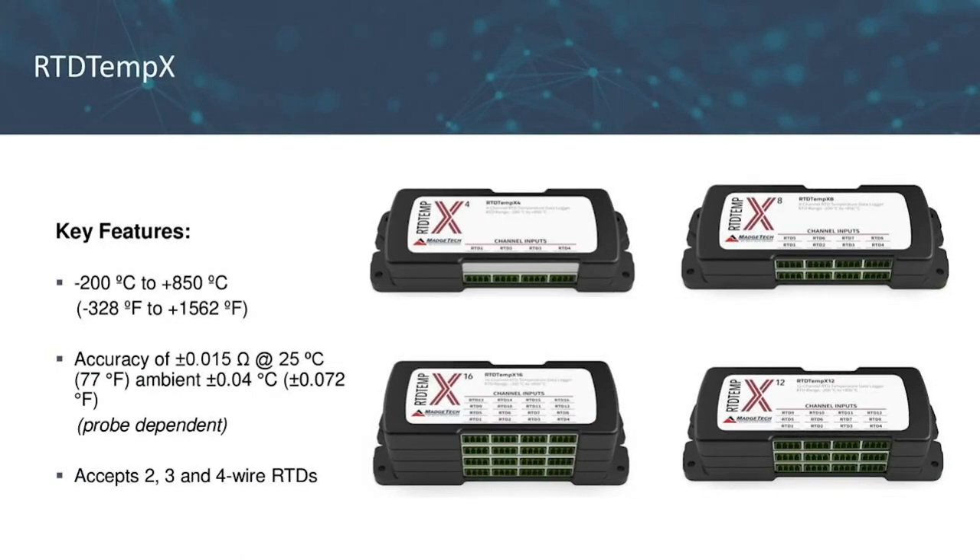Our second temperature logger is the RTD-TempX series. These loggers record temperatures from minus 200°C to 850°C, with a calibration accuracy of plus or minus 0.015 ohms at 25°C. They accept two, three, and four-wire RTDs. The RTD-TempX will be more accurate in its readings compared to the TC-TempX; however, the maximum RTD temperature range is 850°C, while some thermocouple types can reach temperatures well over 1,000°C. When choosing a logger, it's about what temperature parameters fit your application best. More information and comparisons can be found on the product datasheets on our website.